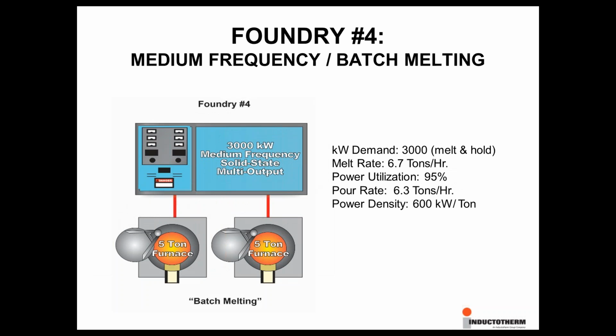Okay, Foundry number 4, which is a medium frequency batch melting system, which I noted previously is 7% more efficient than a heel melting operation. This allows a further reduction of the kilowatt or kVA of demand while still maintaining basically the same production. The higher efficiency combined with higher utilization offered by multi-output power systems results in a demand of only 3,000 kilowatts.